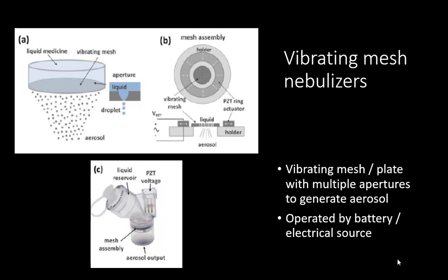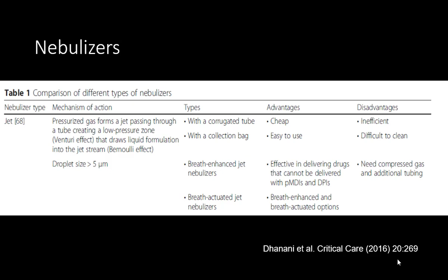So if you use a jet nebulizer, you will get a good droplet size. There are two types of jet nebulizers: one is breath enhanced and one is breath actuated. Breath actuated means the moment the patient starts inspiratory flow, the nebulizer starts working. It is very cheap, hardly 50 rupees, easy to use, effective in delivering drugs. It is better than using a pMDI with spacers. But it is highly inefficient in delivering your antibiotics distally where you want it. You will have to clean it every time, and it either needs a compressed gas or additional tubing.